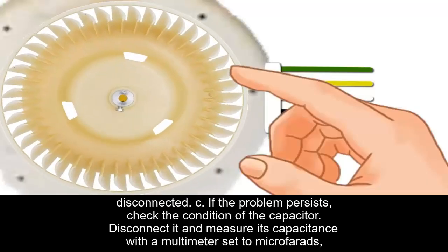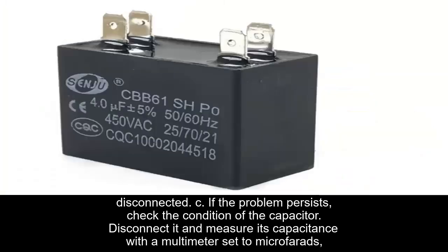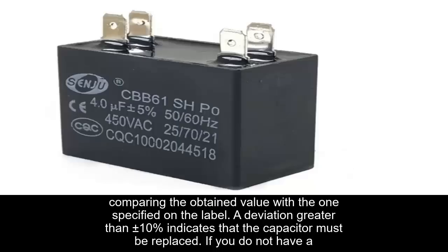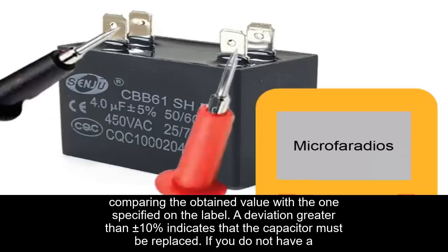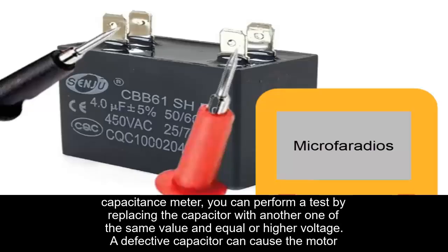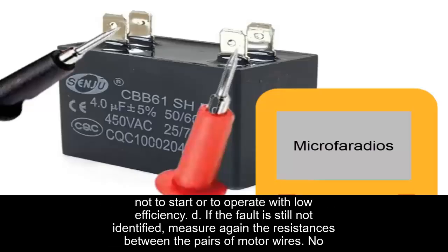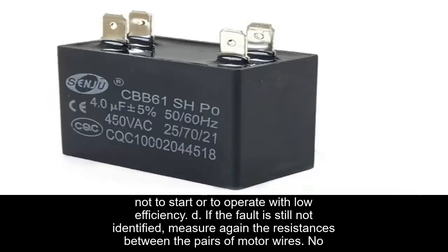C. If the problem persists, check the condition of the capacitor. Disconnect it and measure its capacitance with a multimeter set to microfarads, comparing the obtained value to the one specified on the label. A deviation greater than plus or minus 10% indicates that the capacitor must be replaced. If you do not have a capacitance meter, you can perform a test by replacing the capacitor with another of the same value and equal or higher voltage. A defective capacitor can cause the motor to not start or to operate with low efficiency.